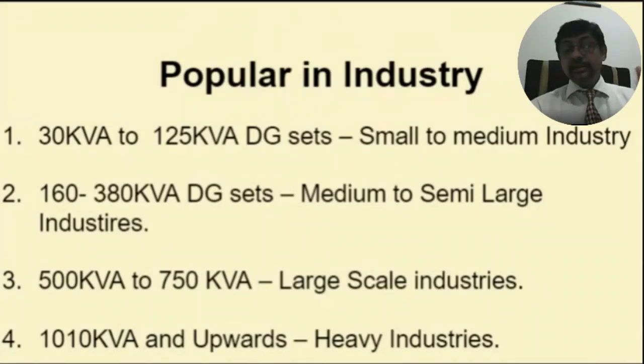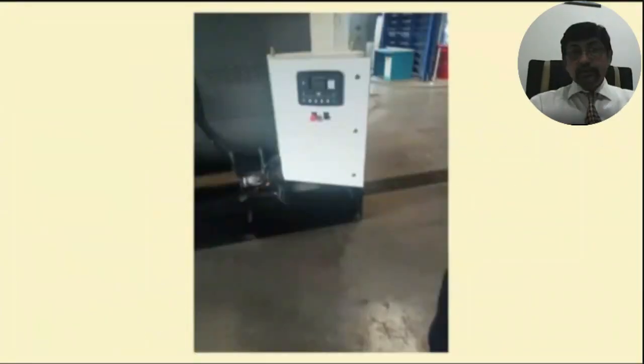Then 160 to 380 kVA is another, medium to semi-large industries. Medium to semi-large is textiles. Then we have the cosmetic industry, chemical industry, pharmaceutical industries, and so on. So they use these kinds of generators, 160 kVA to 380 kVA. And 500 kVA to 750 kVA goes basically to large-scale industries. Large-scale industries are the industries which are catering to the major sectors of India, or any supply chain, or having a requirement where they cannot cut over the power. So they go for a 500 or a 750, and 1000 and upwards is definitely for mass production and for heavy industries. Yes, next. So now these are all generators.